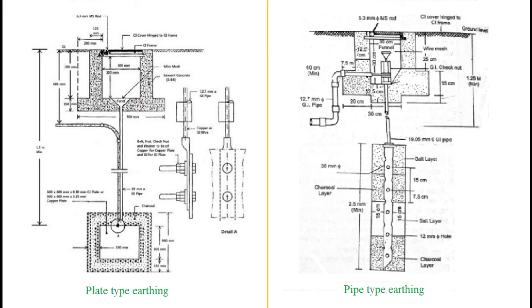When we consider an 11 kV system, at least two independent earth points are necessary. This is because the lightning arrestor needs a separate earth point and the rest of the equipment requires separate earthing. In case of an 11 kV system, an earth strip with rectangular cross section is used in place of copper wire. This earth strip is attached to the pipe using clamps. Such a strip is galvanized and may be welded, and it reaches all the equipment of the substation.